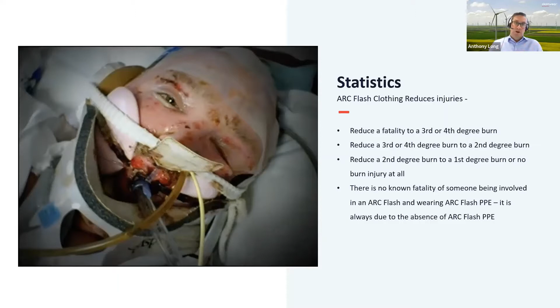Those values, the ATPV and EBT50, are designed to give you the incident energy rating of the clothing at a 50% probability of the onset of a 2nd degree burn. So we're trying to keep the heat passing through to the body under that 2nd degree burn threshold.